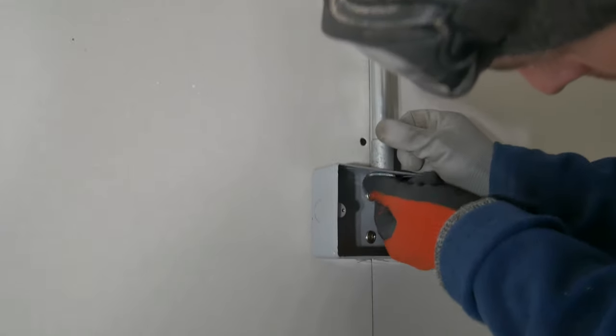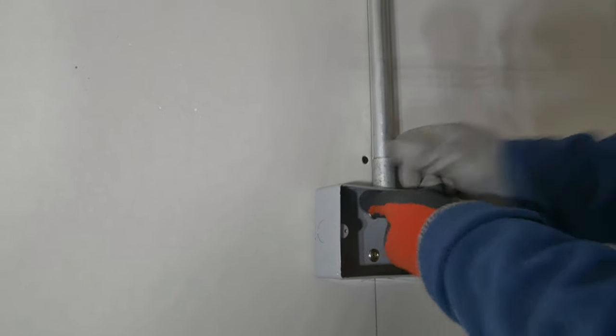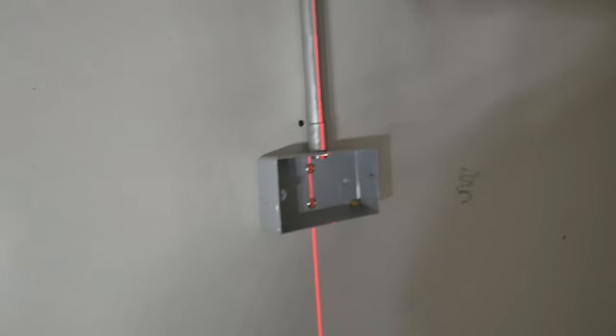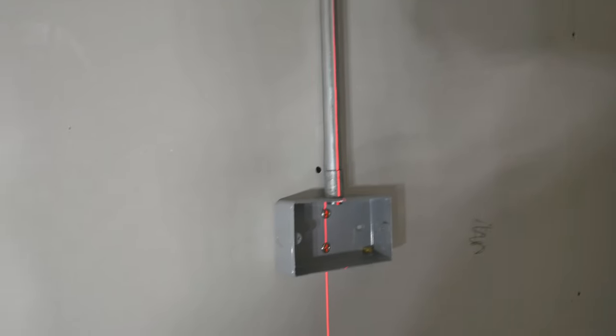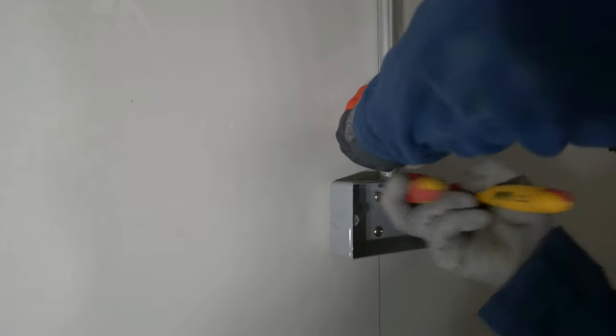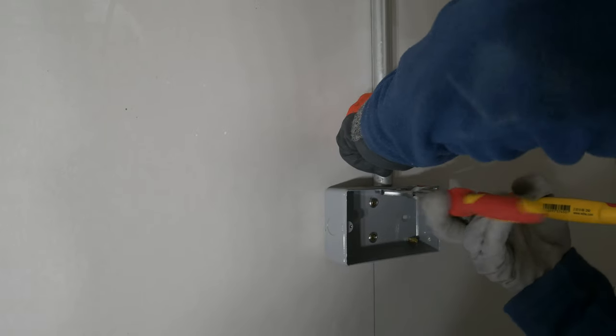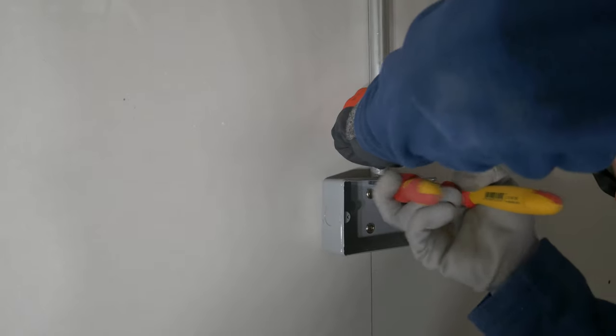Now you can use a double lock ring on this. Sometimes you'll still have a little bit of the metal exposed, so if you're wanting to cover that up, another lock ring over the top can do so. It's not really necessary in my opinion, but if you wanted to do that, the option is there. And once you've got that nipped up to a point by hand, you can then get some pliers or a water pump spanner onto it and just nip it up a bit to give you that nice solid connection on the containment.